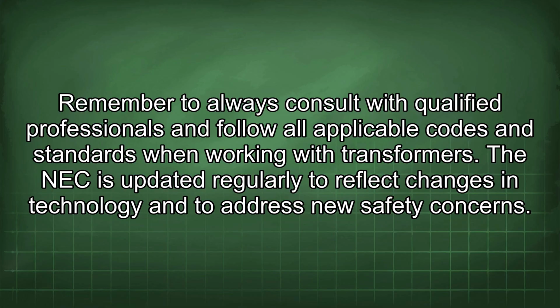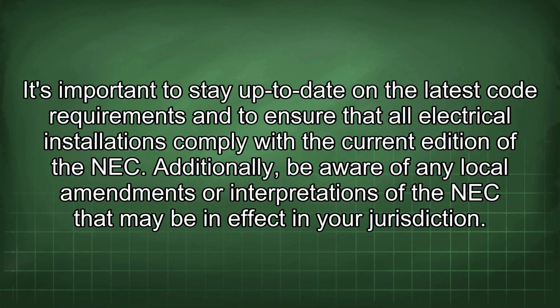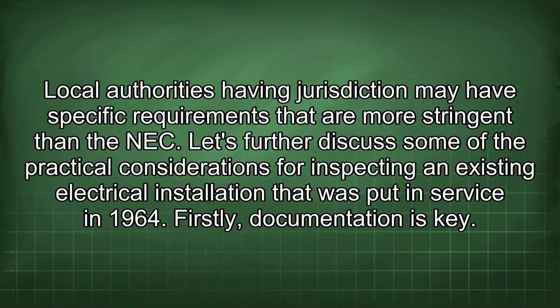transformers. The NEC is updated regularly to reflect changes in technology and to address new safety concerns. It's important to stay up to date on the latest code requirements and to ensure that all electrical installations comply with the current edition of the NEC. Additionally, be aware of any local amendments or interpretations of the NEC that may be in effect in your jurisdiction. Local authorities having jurisdiction may have specific requirements that are more stringent than the NEC.